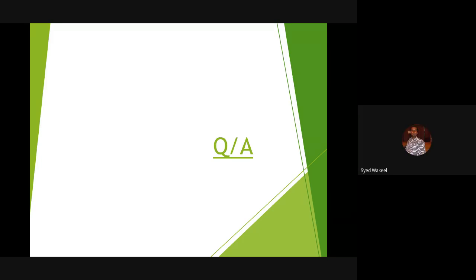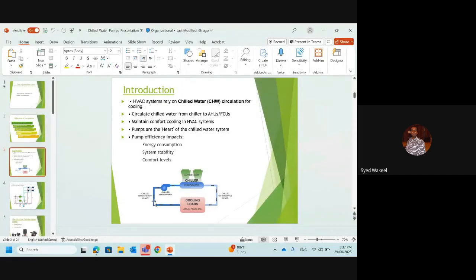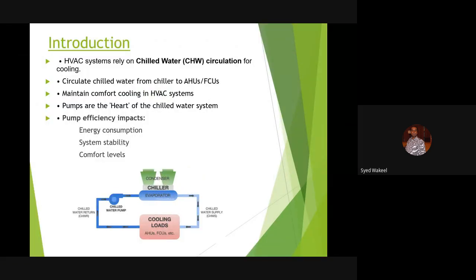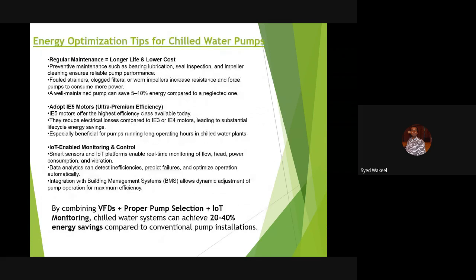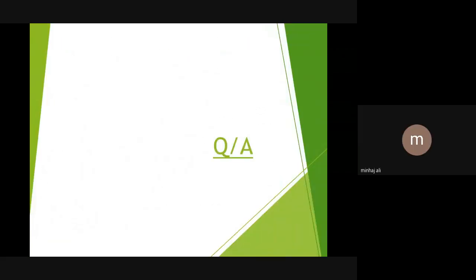Yes, right. Okay. So to answer this, during the testing and commissioning, after the system is stabilized, you can keep your chemical dosing pump cutout pressure and cut-in pressure one bar higher than the system pressure. That means if your pressure is 1 bar higher than the system pressure, you will be able to pump in the chemical. I'm not getting. System pressure means it will be on the suction side, before? Correct. Let's say your suction side pressure is 3 bar. When the suction pressure is 3 bar, in the chemical dosing pump system you can keep 4 bar, because then the 4 bar pump can pressurize the 3 bar system. Yes. That's the answer.